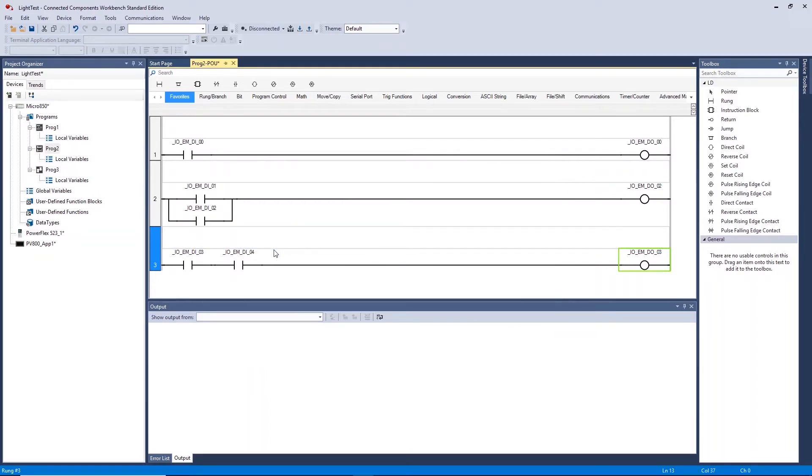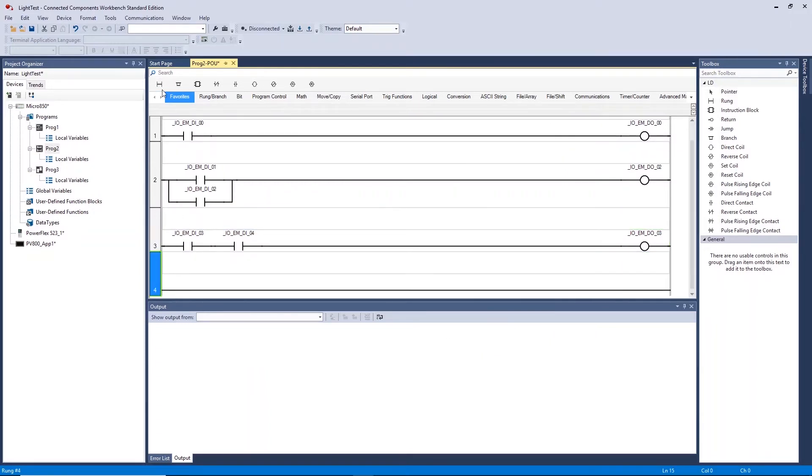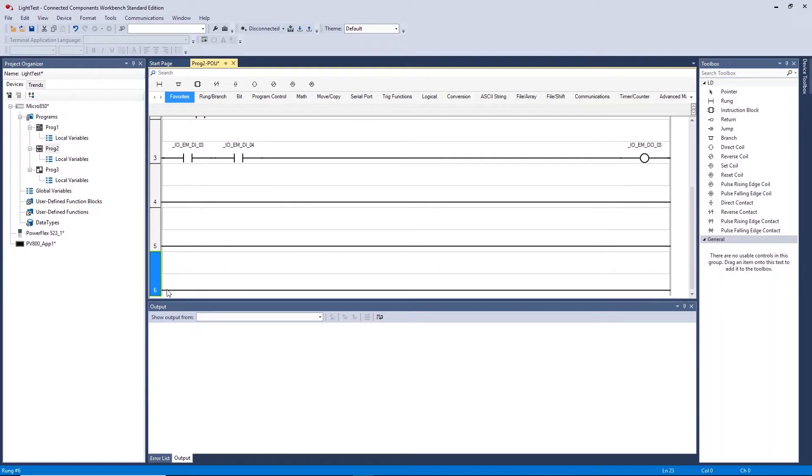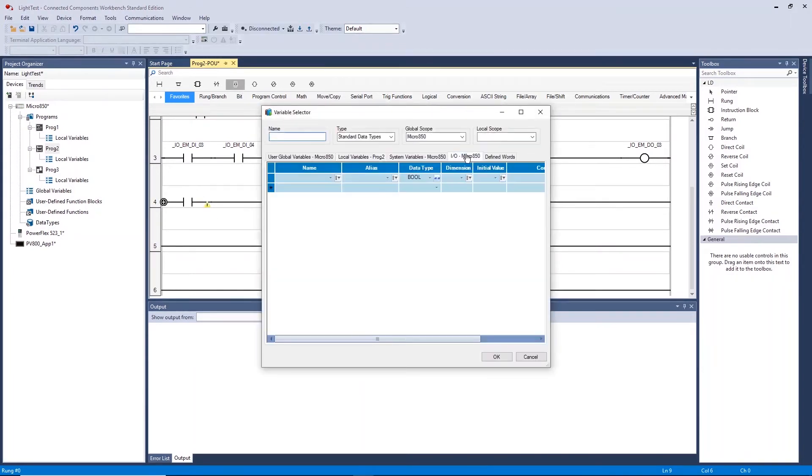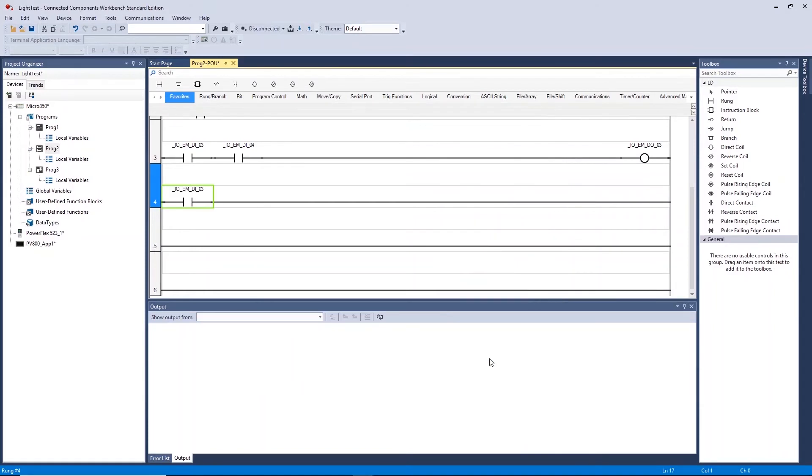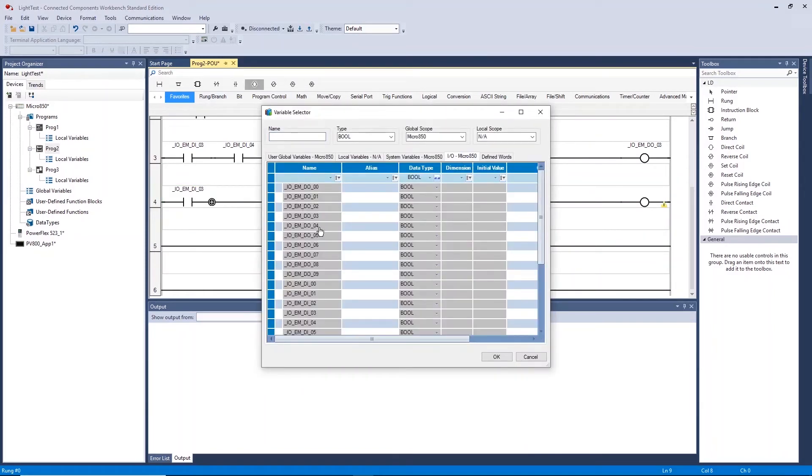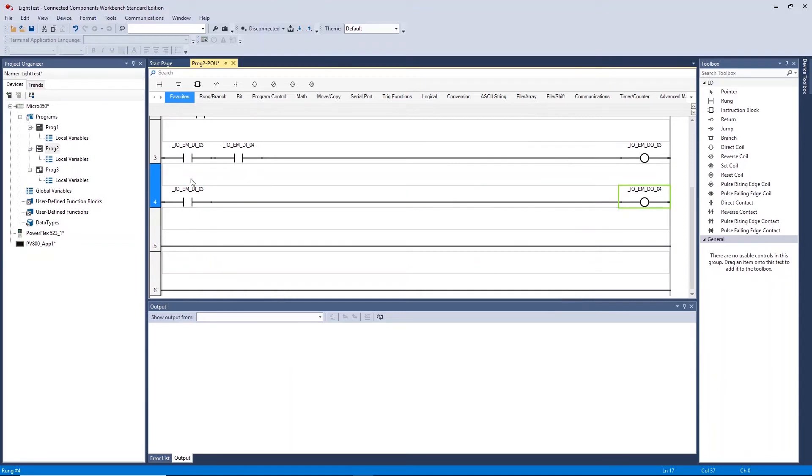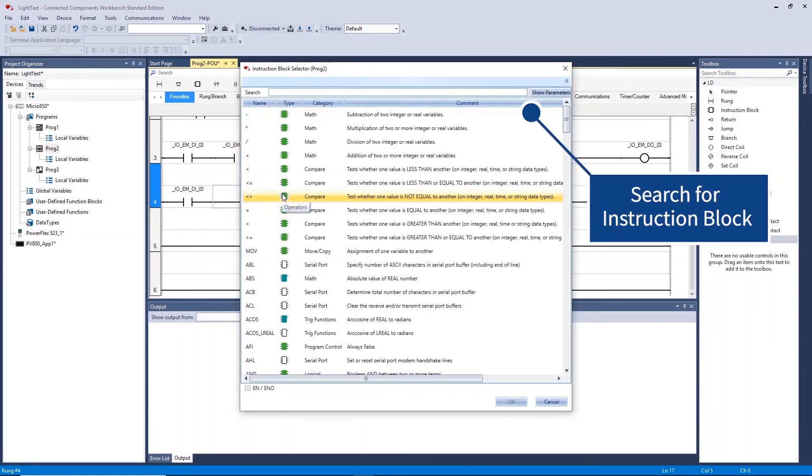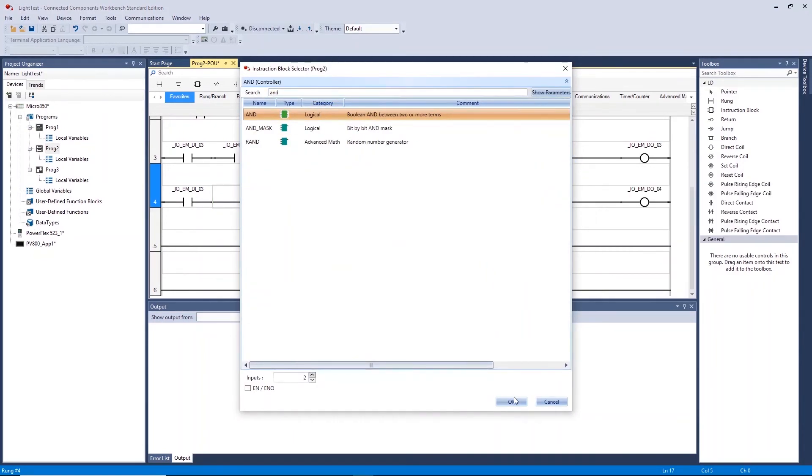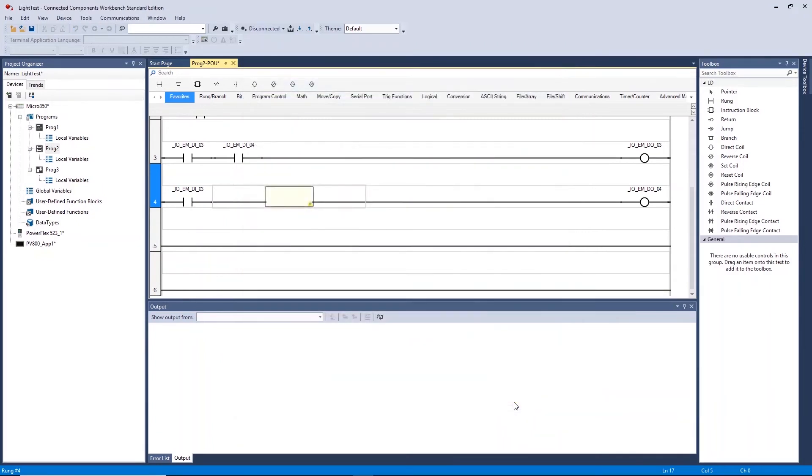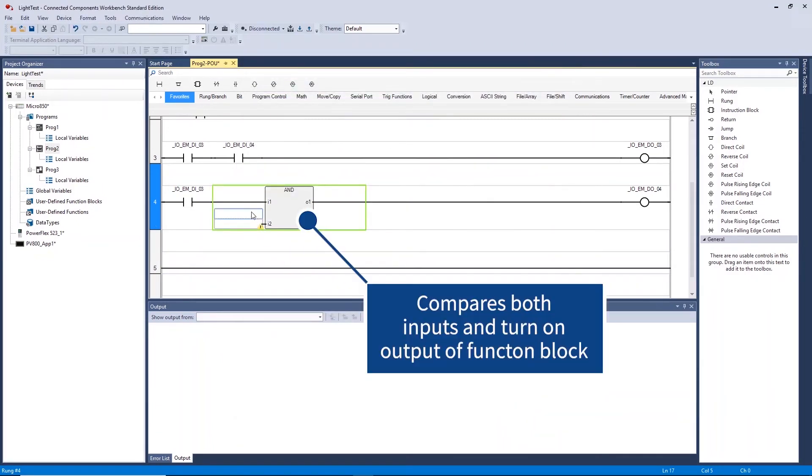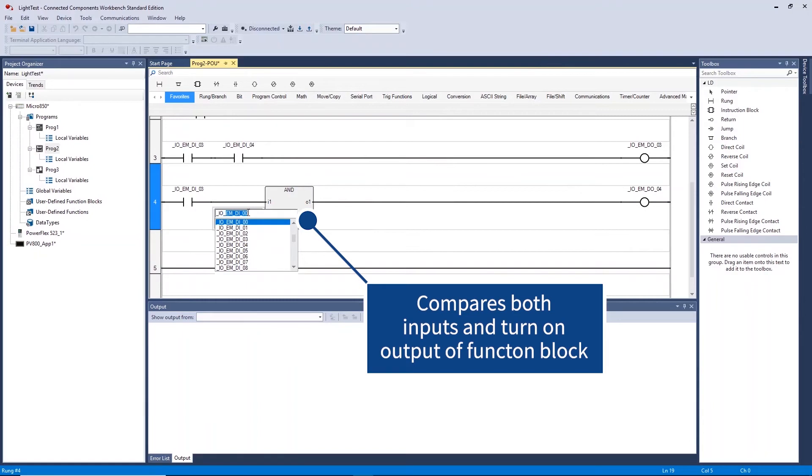We will now create some AND logic using the pre-existing function blocks. Click on the rung you want to add the pre-existing function block to and click on the instruction block icon in the toolbox. Select or search for the function you are after. This AND function block compares two inputs and turns on the output of the function block when both are high.